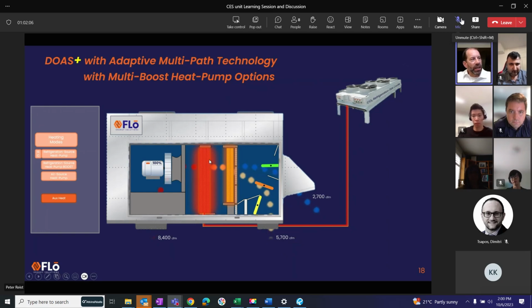Now, in your project's case, we can't run these two in conjunction, so we'll have to have one or the other at any one time. So we could start with reclaim, but once we need more heat and need to go to your water source heat pump, we'll need to shut that one off and go over to the heat pump. The reason being is they both raise to about the same temperature. So when one's leaving temperature is the same as the other one's leaving temperature, you get no net benefit, because you need a temperature differential across a coil. So we'll only be able to use one or the other at any given time in the unit, but we still will need them both existing for various reasons.